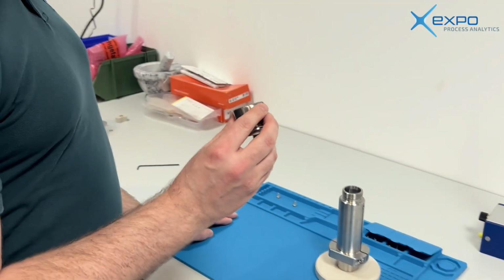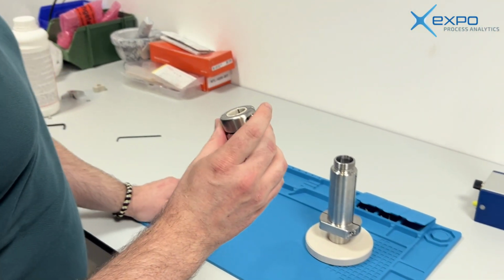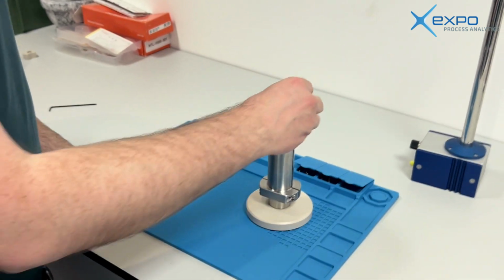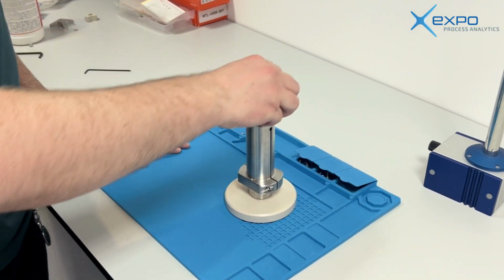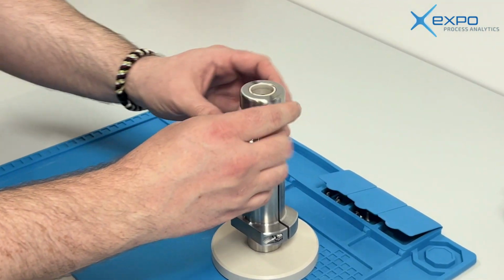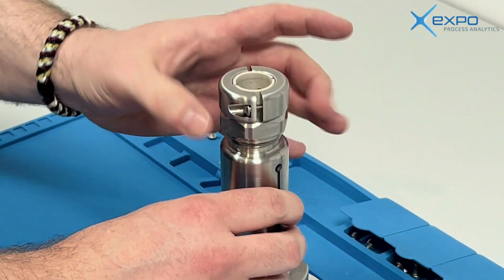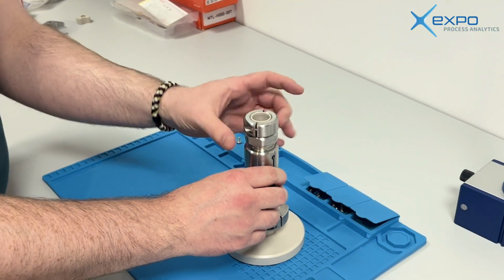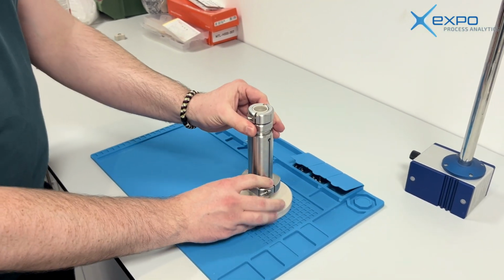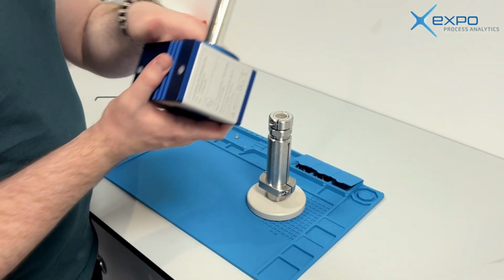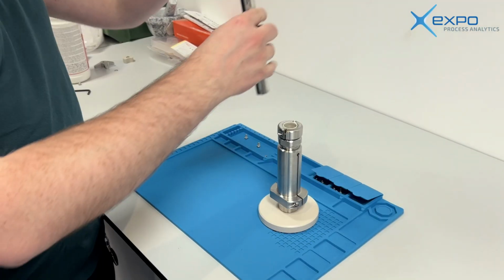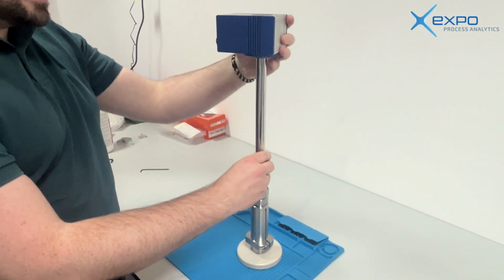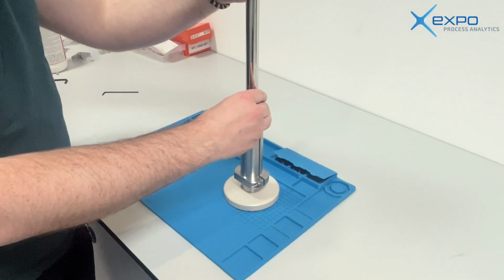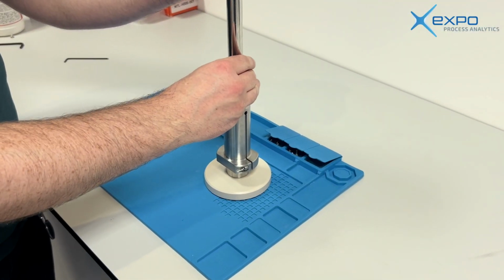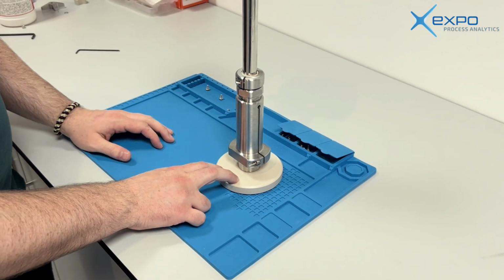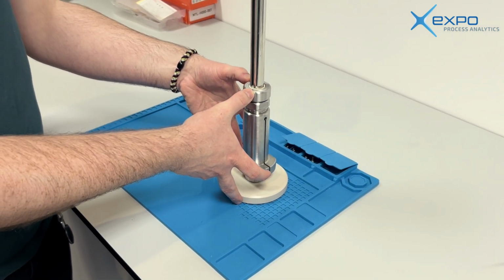Okay, so at this point, again, you have your compression fitting and your collar and your sleeve. So then you'll thread this back onto the device, or back onto the setting tool, excuse me. Again, we'll torque it up to the intended value, the final value. But I'm just going to tighten it loosely for now. And then you'll feed whatever probe you intend to use into this compression sleeve, into the setting tool, being gentle with it, but let it fall down and bottom out on the polymer base, because that is now mimicking the distance to the front of our device.